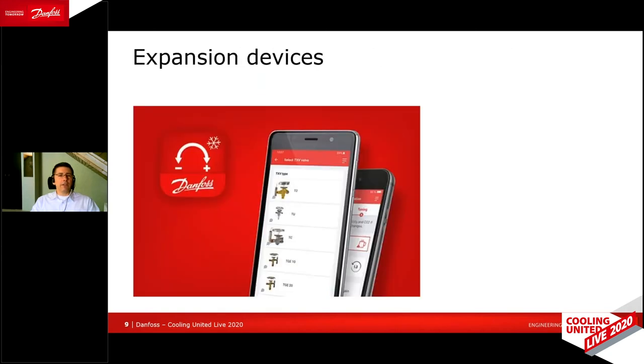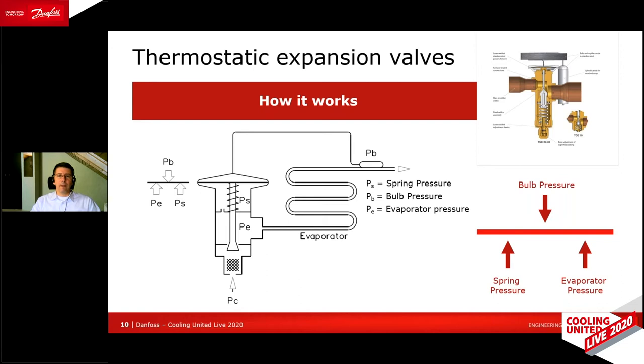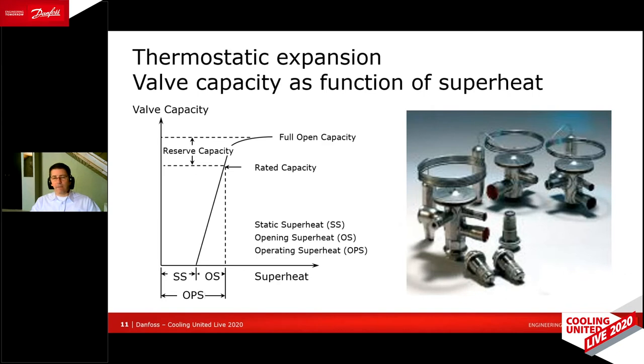How do we control the injection of refrigerant into the evaporator? With an expansion device — for example, a thermostatic expansion valve. The bulb pressure presses downwards, while evaporating pressure and spring pressure from the superheat setting push from below. When the bulb gets warmer, more pressure opens the valve — so more superheat gives more valve opening. This leads to a linear relationship: the more superheat, the more the valve opens, until it reaches maximum opening or rated capacity.